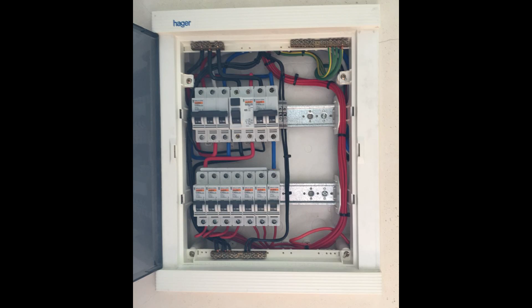The earth path is not a fault path. The fault path is to neutral, because the earth would bond in the council panel, in the council supply board, meter board. It would bond to the neutral, and it's essential, because you're not going to be able to trip a breaker to earth with a 25 ohm earth ground rod resistance. So what you're saying is if we opened the cover and removed the interior cover on the console or the main panel, we would find a ground bar and a neutral bar, and they're tied together at that point. Yeah. Those two tied together go down to a common point, in the US a common point box. And then from that box, it goes to the ground rod. And in that common point box, the TV, gas line, and water lines all come together as one ground.